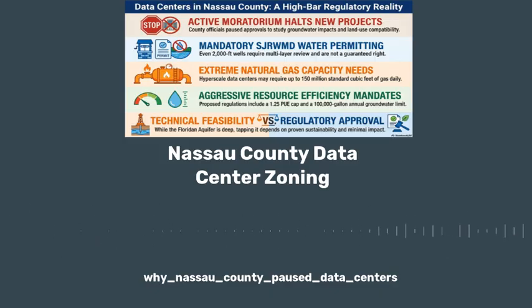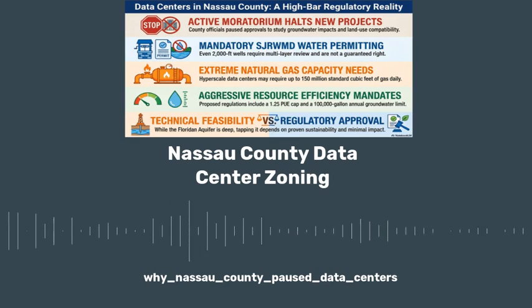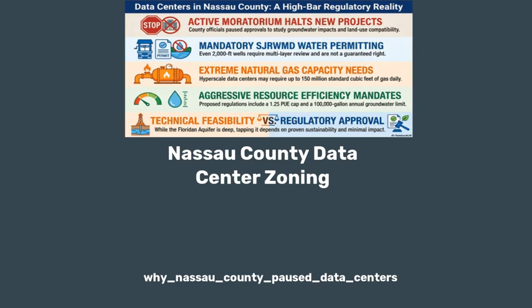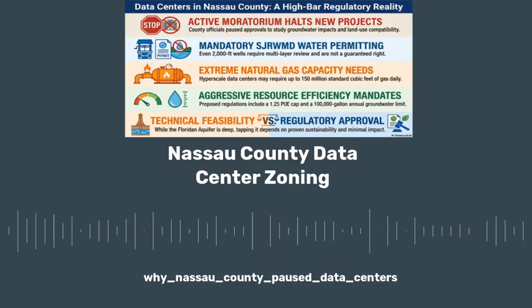Exactly. And the customers downstream of the data center, the paper mills, the local distribution hubs, suddenly watch their gas pressure die. So the pipeline operators have to calculate, do we have enough available compressor horsepower upstream to push an extra 150 million cubic feet of gas hard enough to overcome that massive draw while keeping the downstream pressure perfectly stable? It sounds like an incredibly intricate, almost fragile puzzle. You can't just guess. You need the exact location of the proposed data center tap, down to the specific milepost on the Callahan line, to even begin running the pressure models. Which is precisely why Nassau County enacted the moratorium. They cannot just look at a map and say, sure, we have gas lines, bring on the gigawatt facilities. They have to rigorously research the reserve capacities, the compressor horsepower, and the contractual limitations of their backbone infrastructure before they can confidently zone for these types of behemoths.